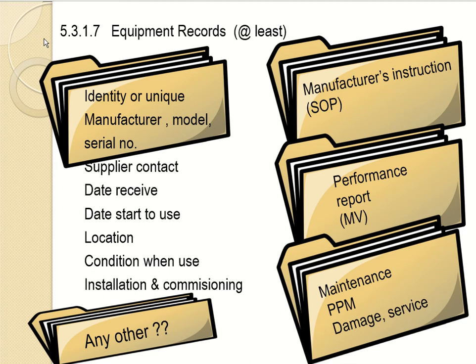For clause 5.3.1.7, it stated the equipment records. So at least it should have these criteria: the equipment records, identity or unique, manufacturer, model, serial number, and many more. You can read it by yourself. Should also include the manufacturer instruction, which is covered in the standard operating procedure. Should have the performance report, yeah, of the equipment, plus the test included in it, which I will cover in the next lecture with the verification. And also the records should cover the maintenance of the equipment, PPM, damage and service that happened to the equipment.